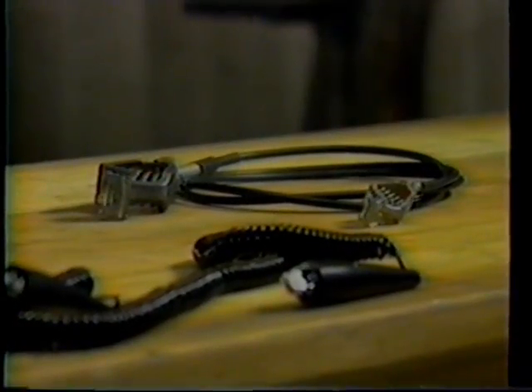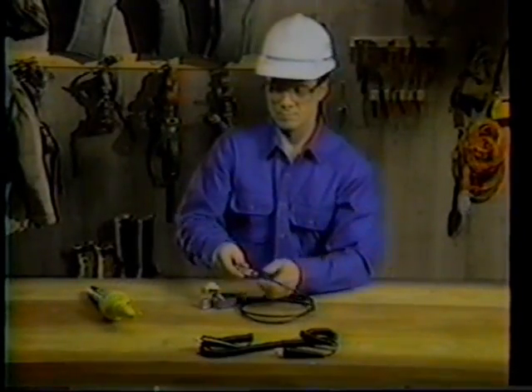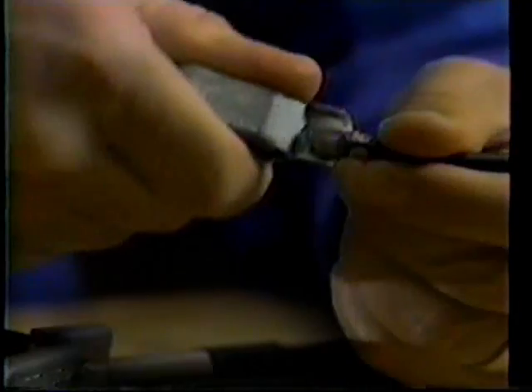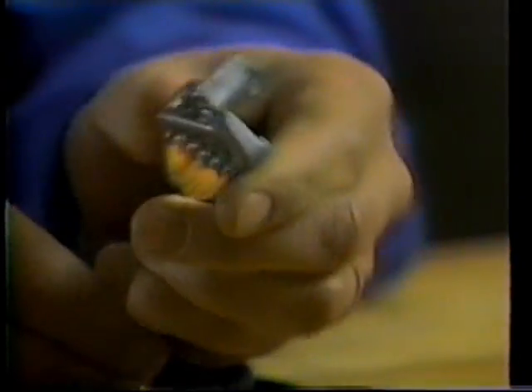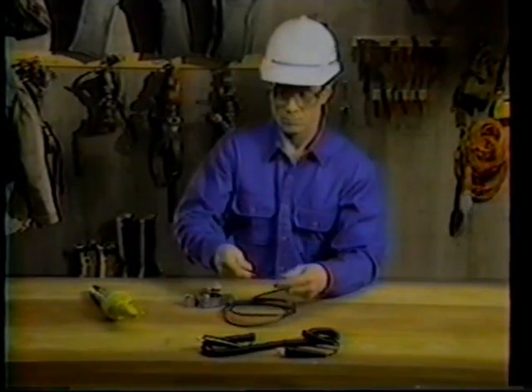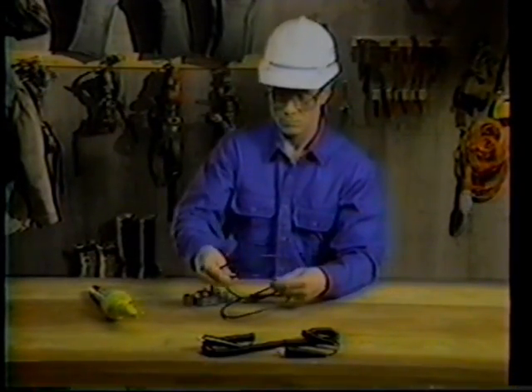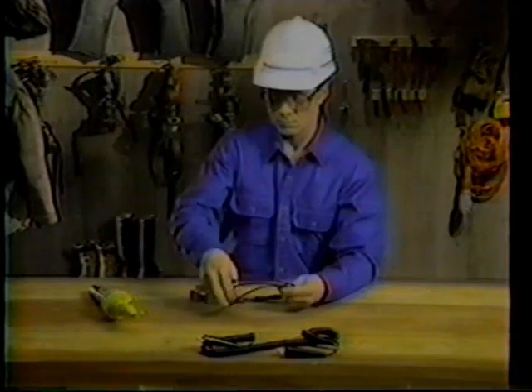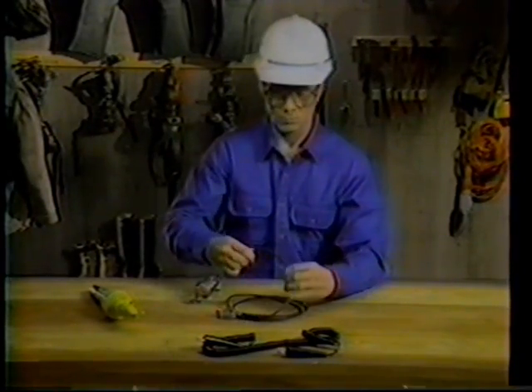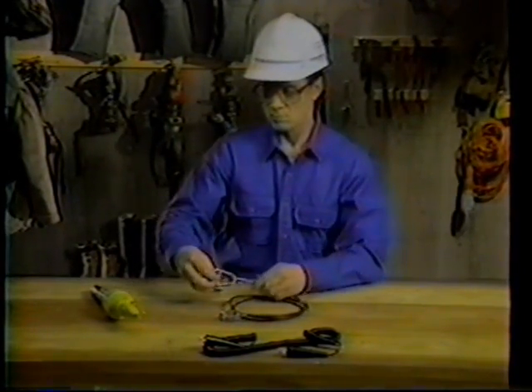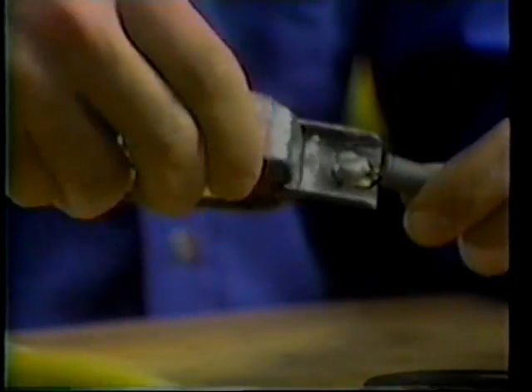Your B temporary bond should be examined to make sure it is not frayed and all connections are secure. Wiggle the connections to feel for play. Check for spring tension. And run the wire through your fingers to feel for burrs or breaks in the plastic insulating cable. Also check to see that the copper flashing is inside both clips.